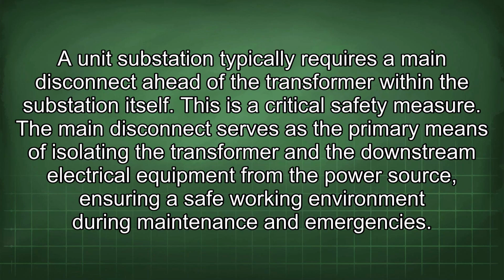A unit substation typically requires a main disconnect ahead of the transformer within the substation itself. This is a critical safety measure. The main disconnect serves as the primary means of isolating the transformer and the downstream electrical equipment from the power source, ensuring a safe working environment during maintenance and emergencies.